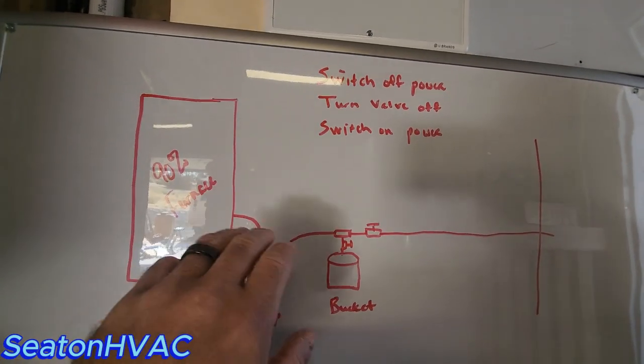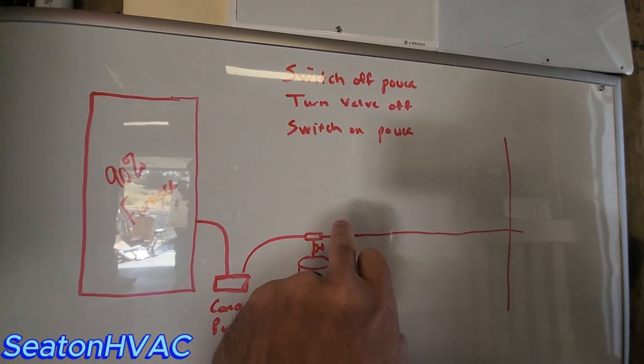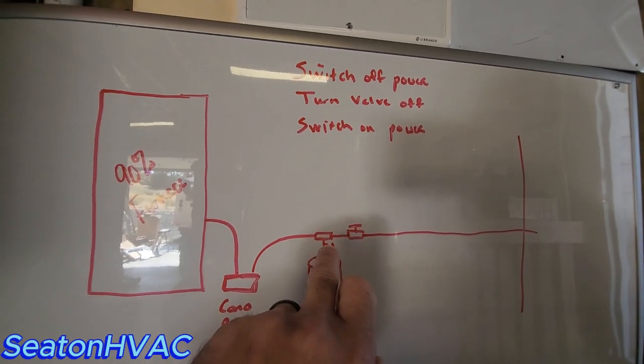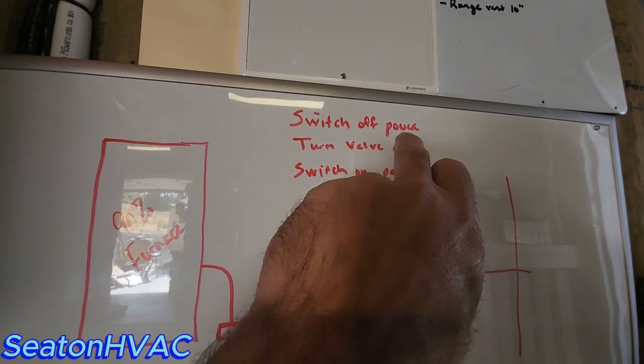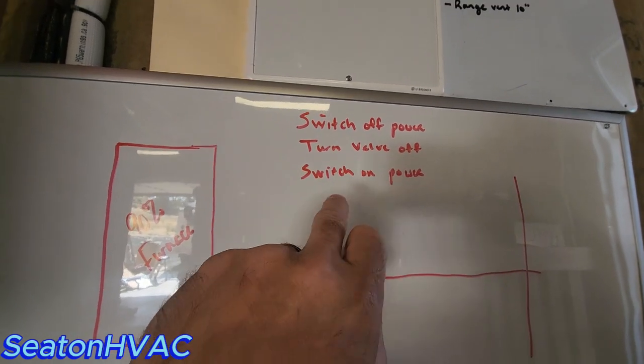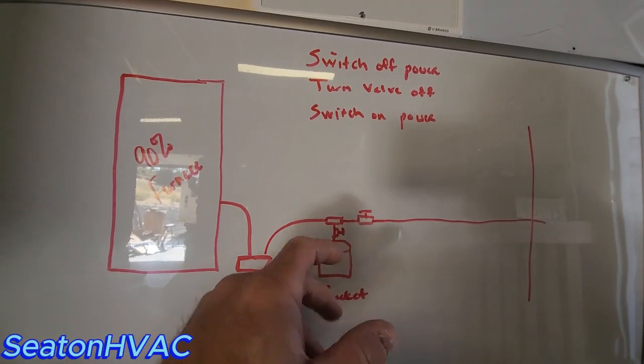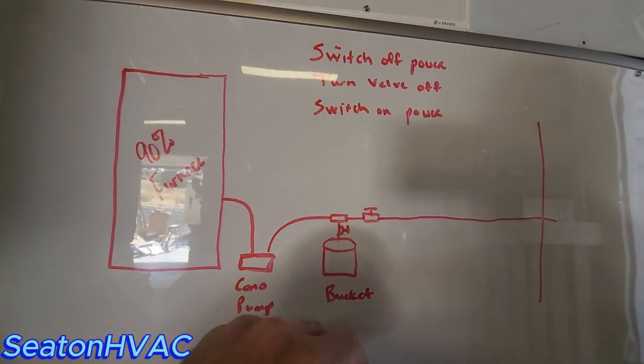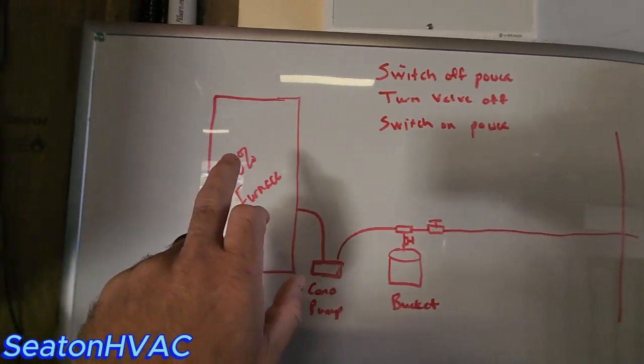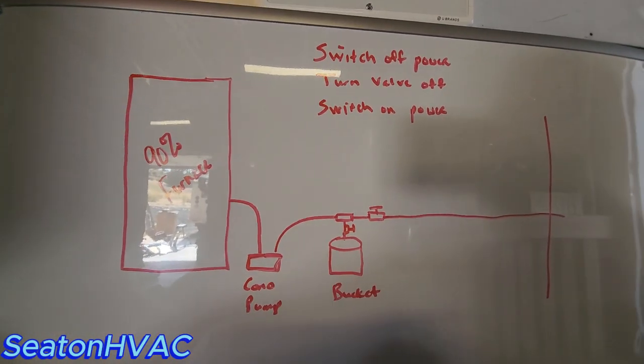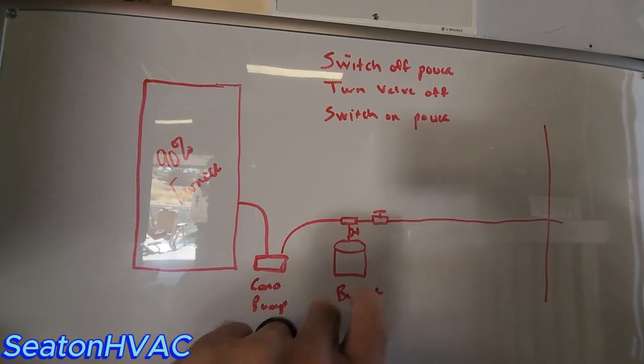But let's say the customer calls and says their line froze up. What they can do is shut this valve off and turn the other one on. What they need to do though is switch the power off, turn the valves, then switch the power back on. That'll get their heat going - with a 5-gallon bucket, that'll get them through the night or a couple days, or however much condensation the furnace makes, and that'll keep them going.